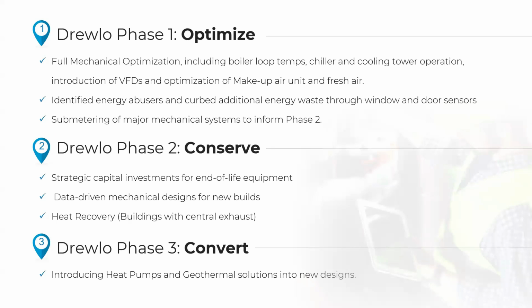Drewlo doesn't have a lot of buildings this applies to, but there are a lot of multi-res buildings in Ontario with this opportunity—to add heat recovery to buildings that have central exhaust. Central exhaust means pulling all the exhaust from the suites, bathrooms, and kitchens up through vertical ducts and fans on the roof. For any multi-res building designed that way, which is probably somewhere between 30 to 50% of all multi-res buildings in Ontario...